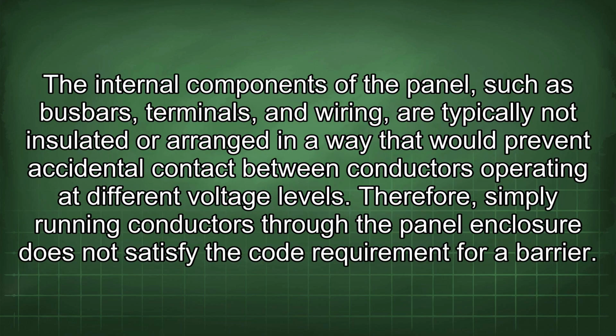The internal components of the panel, such as busbars, terminals, and wiring, are typically not insulated or arranged in a way that would prevent accidental contact between conductors operating at different voltage levels. Therefore, simply running conductors through the panel enclosure does not satisfy the code requirement for a barrier.